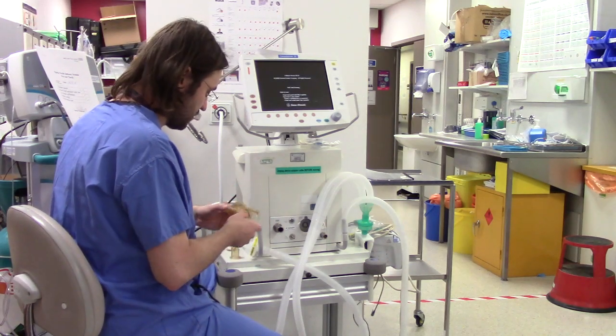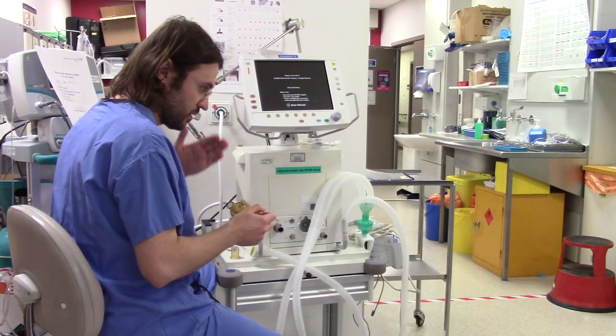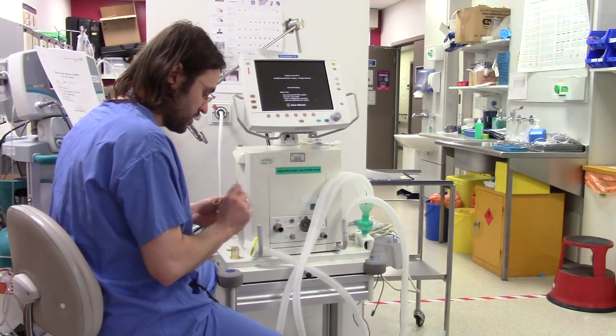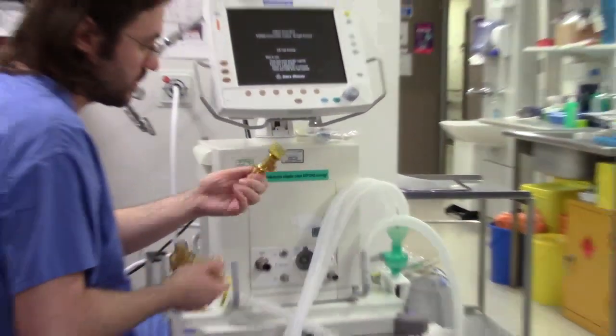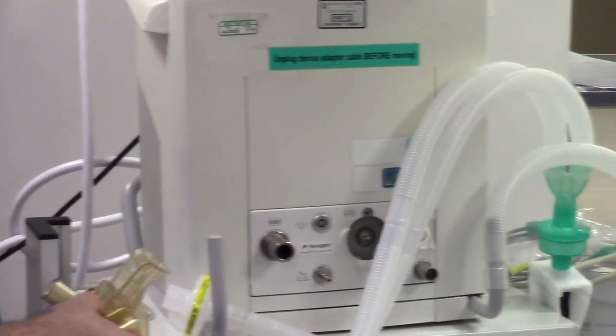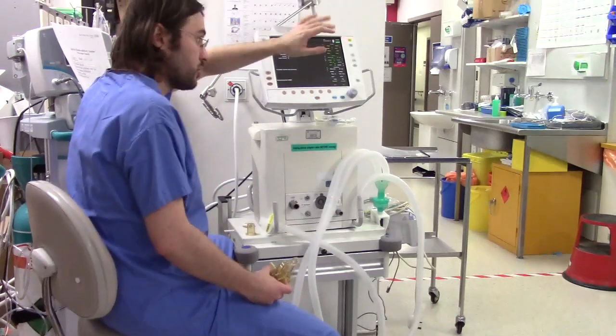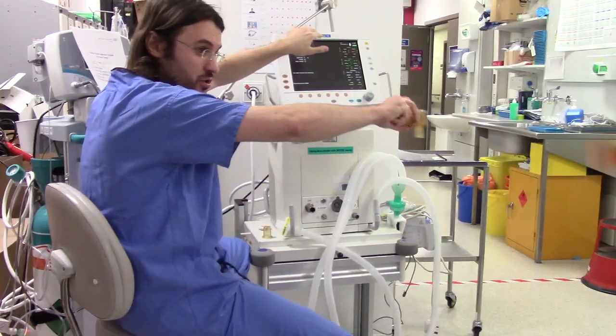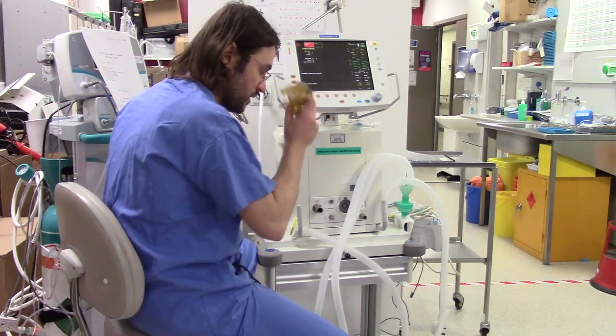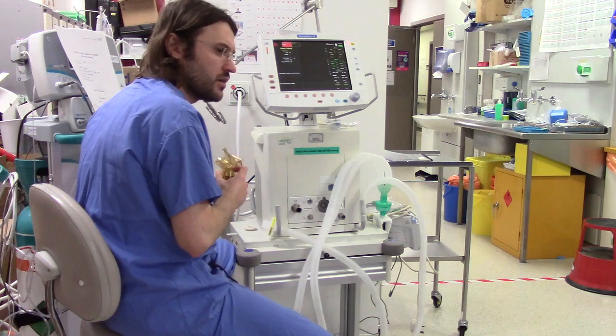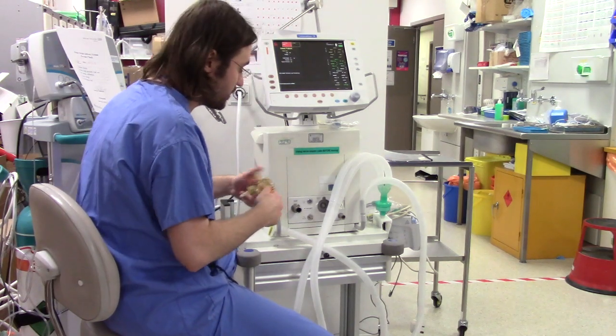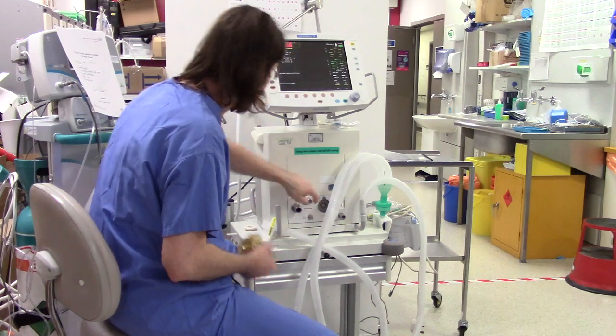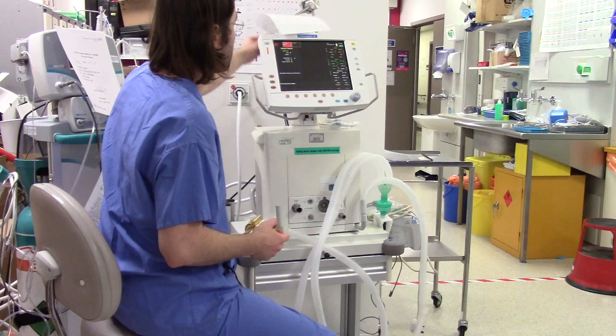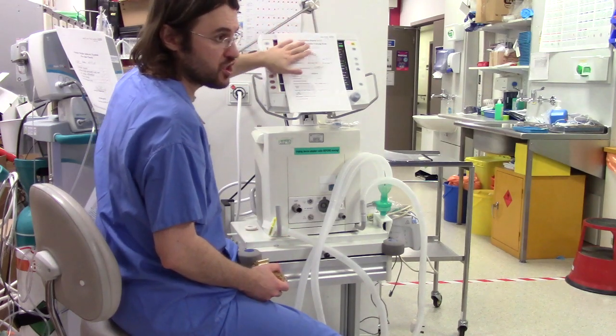So now about this block. This block is called exhalation block. So this block is responsible for the exhalation of the patient, and at the same time this block contains this part, which is called the flow sensor. So when you guys collect these ventilators from the equipment room, our main equipment room, you know where it's located? As you go down the corridor on the right hand side before you actually go to ITU or HDU. Yeah, so that's the place where we keep all the main ventilators, hemofilters and other devices. You already find it with the block attached over here, and with a certificate saying that it's been decontaminated and it has been checked and it's safe to use.